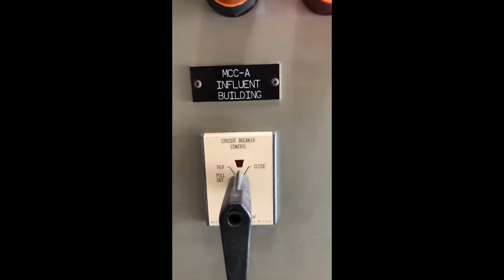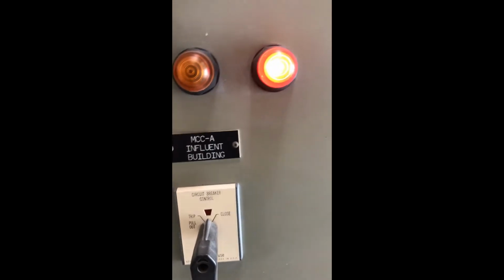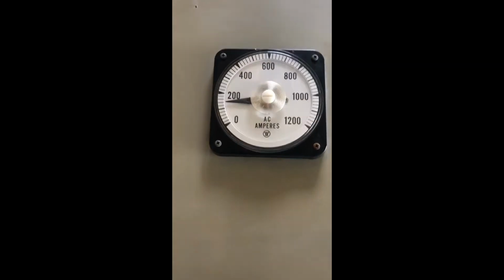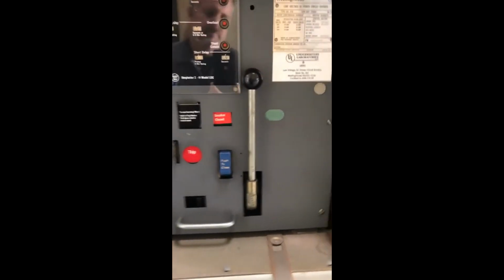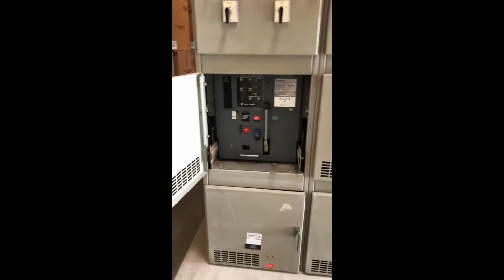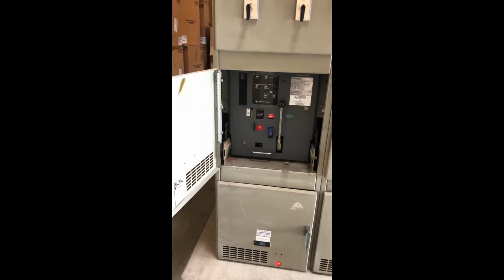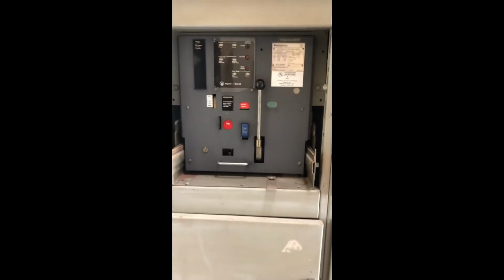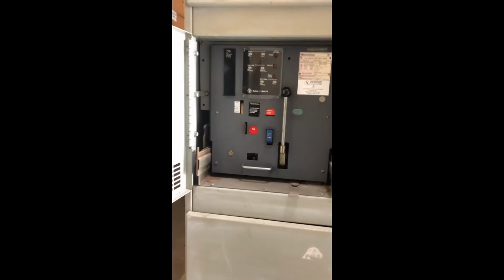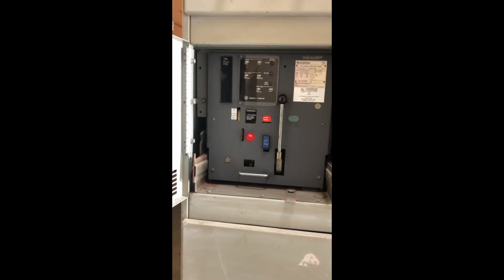This here is MCC-A. It's got a little bit of a load on it. So that's the controls, and then the actual circuit breakers are down here. And I'll back up a little bit. So that's the draw out circuit breaker. That circuit breaker actually racks out of the panel completely, and we covered this a little bit. All the different settings that are available.